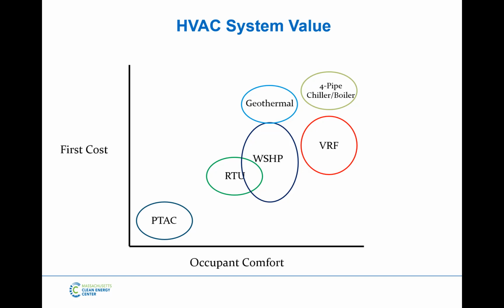If we look at a 400 to 500 ton building, we have those with VRF in this immediate area. Anything above that, the larger 4-pipe chiller boiler systems currently make more sense. Below that is where VRF can have a first cost advantage. A lot of that has to do with, number one, what JS showed, the hard water piping versus flexible copper, but also the control system required. That's actually going to be a topic of this presentation later on, the difference in controls and how a lot of them are built in, and you don't need a complete secondary control system. You may want one, and we can work with it, but it's not required like it is with a 4-pipe chiller boiler. So that's where we'll see the cost savings.